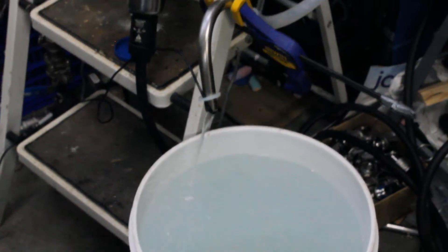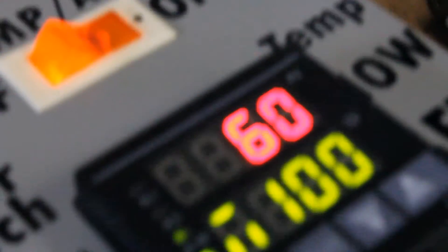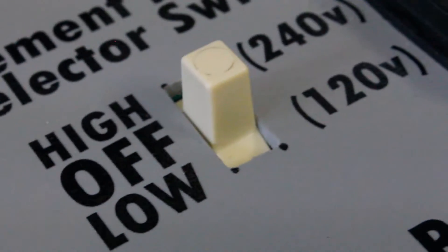Alright, so I'm gonna reset everything and then we're gonna do it again at the full 5500 watts and see what happens. We have the same liter per minute flow rate going, I didn't change any of the valves, and again I have the manual mode set at 100% duty cycle. The PID is trying to fire the element right now but I don't have the switch enabled.